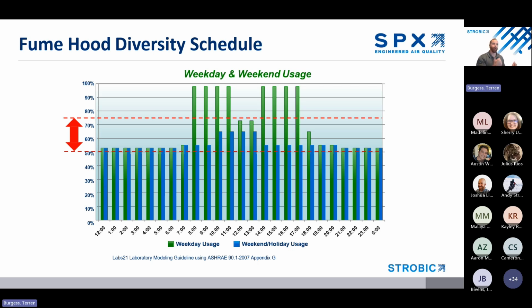It's going to be larger fans, oversized ductwork, higher energy costs, even though the actual demand, the true diversified demand, could be far less. So applying these diversity factors, if you will, allows us to right size the system to handle what's going to be a more realistic peak condition, as well as a realistic demand diversity. A couple of benefits. First, it reduces capital costs, right? Smaller fans, motors, and ducts mean a lower initial construction cost. But second, and I would argue more importantly, it's going to translate to a reduction in ongoing energy use because the system is designed around true demand rather than a worst case scenario that infrequently happens, right?